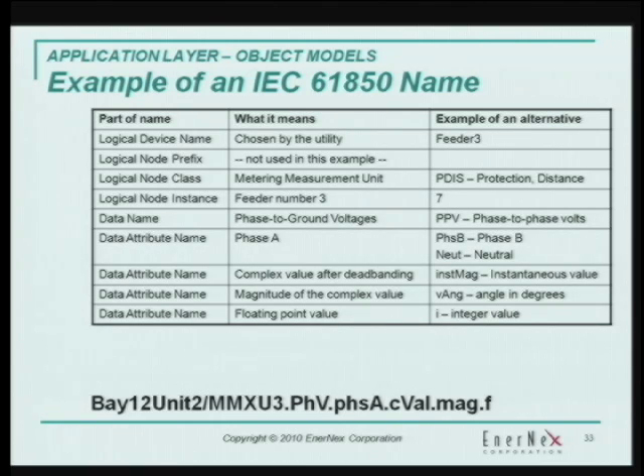So here we've got a top-level device that may be an addressable device. This is a name for the third instance of a device that does measurements. Then we can get down to the phase voltage, one channel, phase A — the absolute value of the magnitude and the floating point representation of it. Just like drilling down into a tree in an SNMP-type structure, it's a similar kind of thing here.